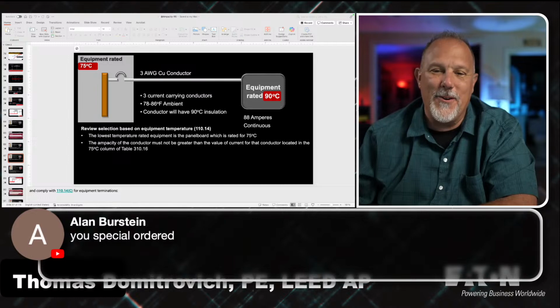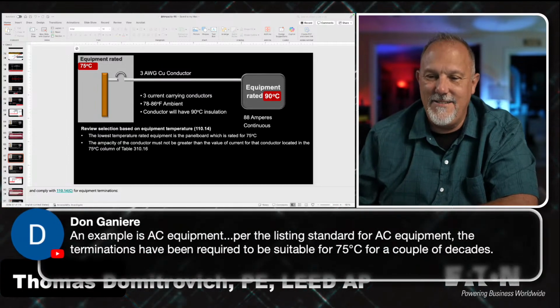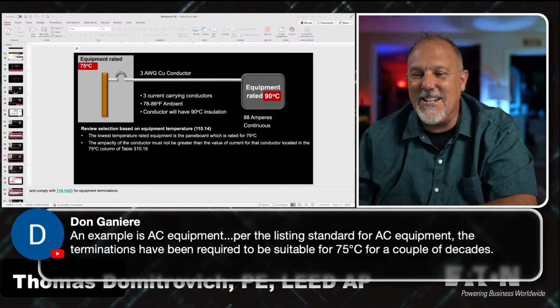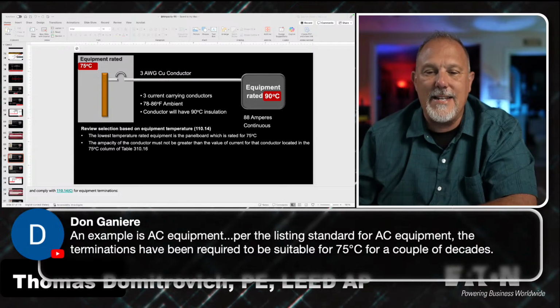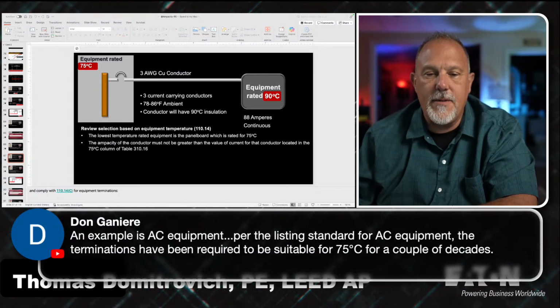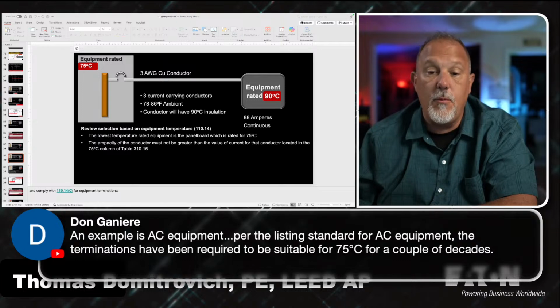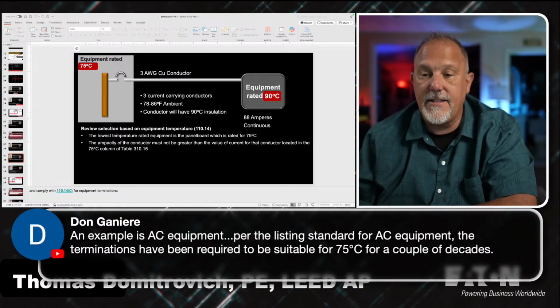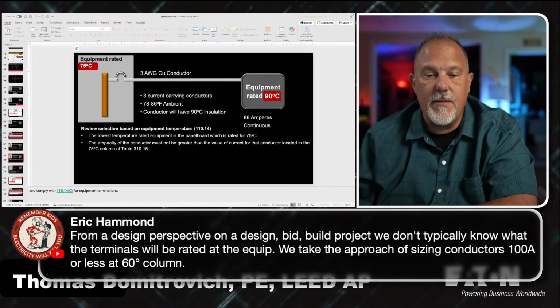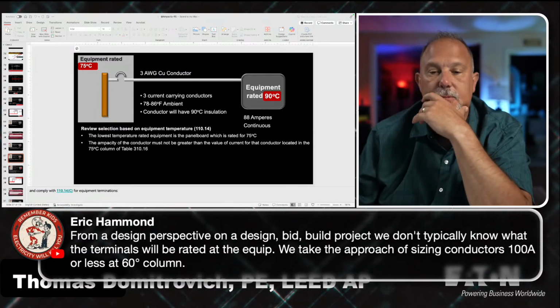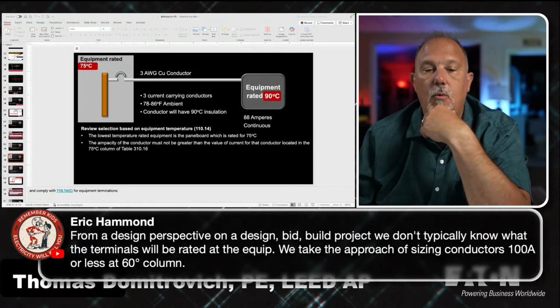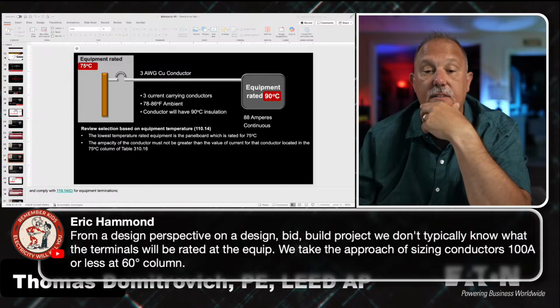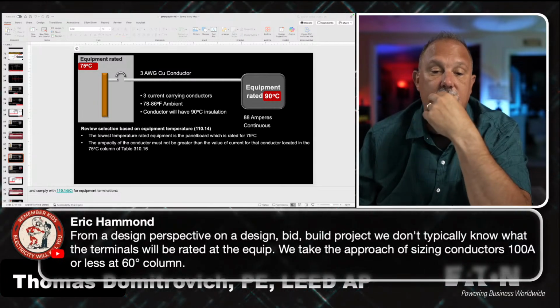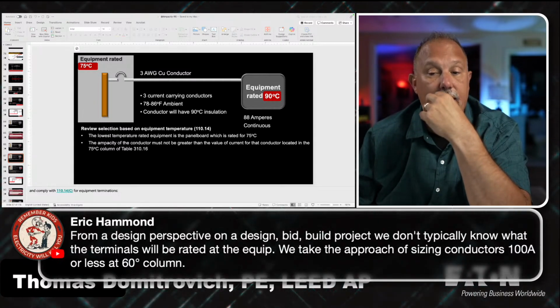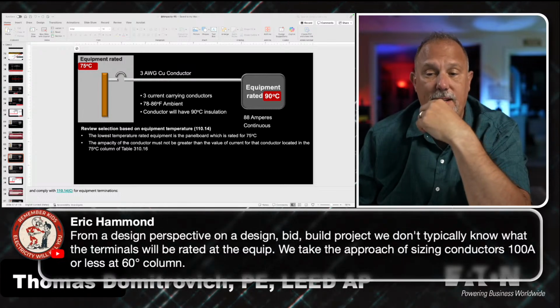I special ordered. No, I didn't, Alan. An example is AC equipment: per the listing standard for AC equipment, the terminations have been required to be suitable for 75 for a couple of decades. Yep. Eric Hammond says, from a design perspective, on a design-bid-build project, we don't typically know what the terminals will be rated in the equipment. We take the approach of sizing the conductors 100 amps or less at 60. Eric, good point.